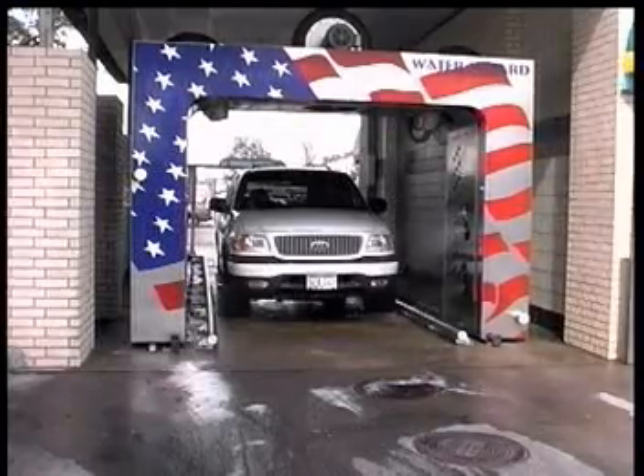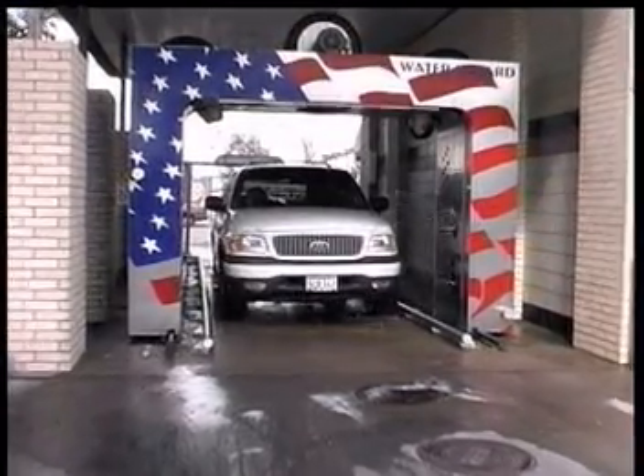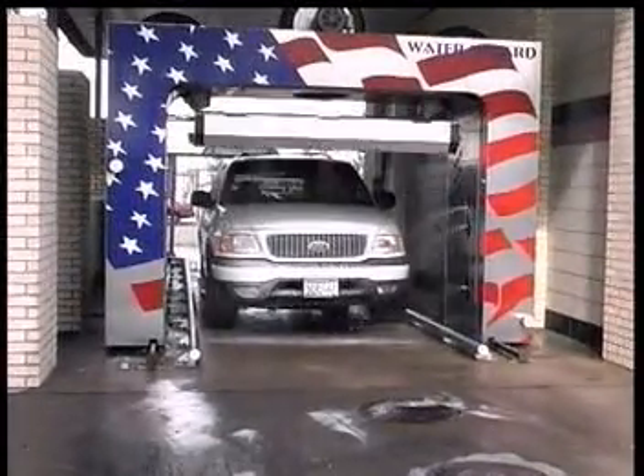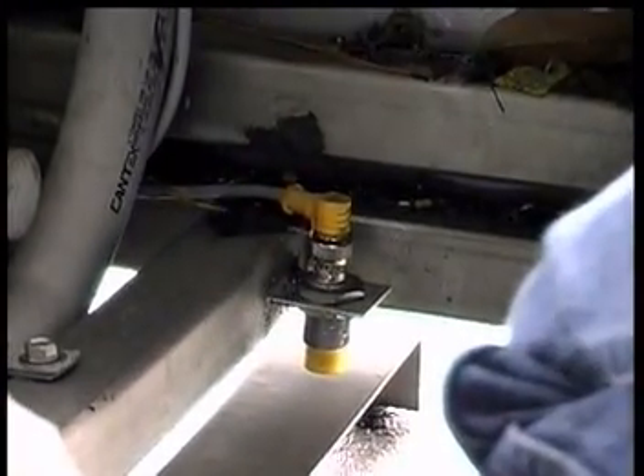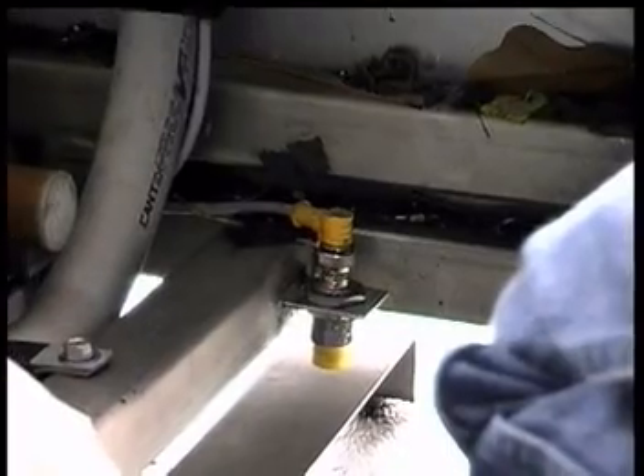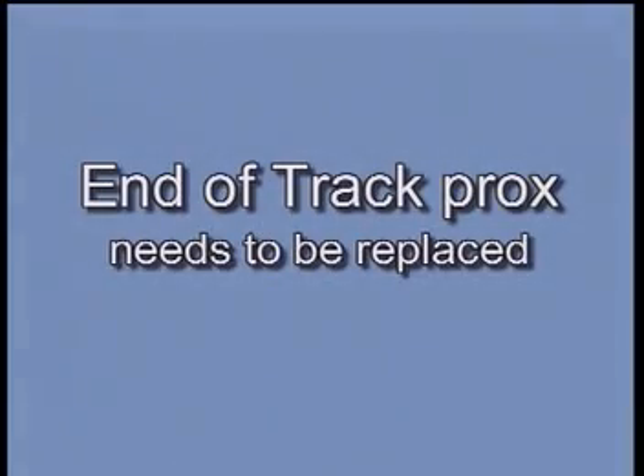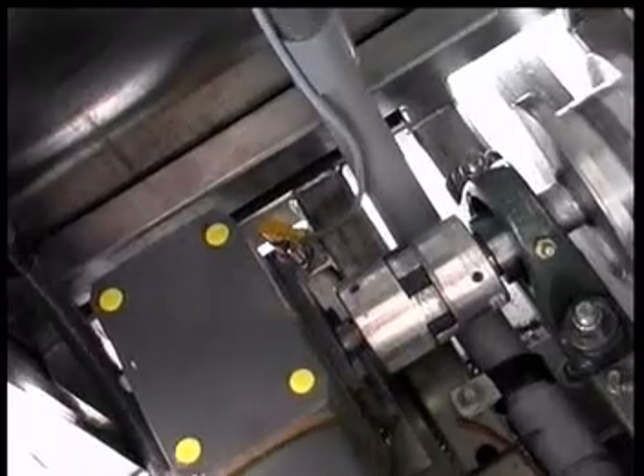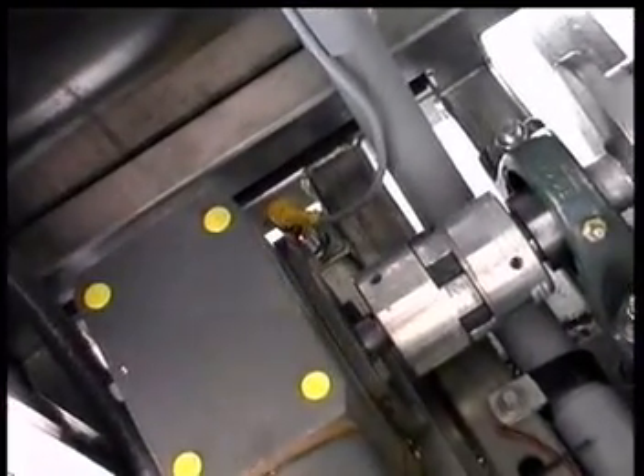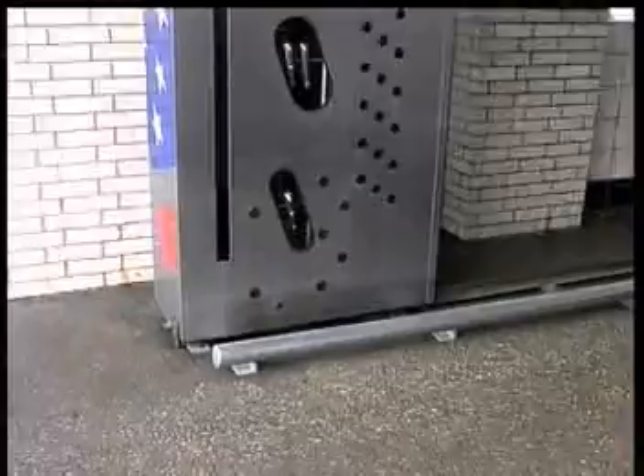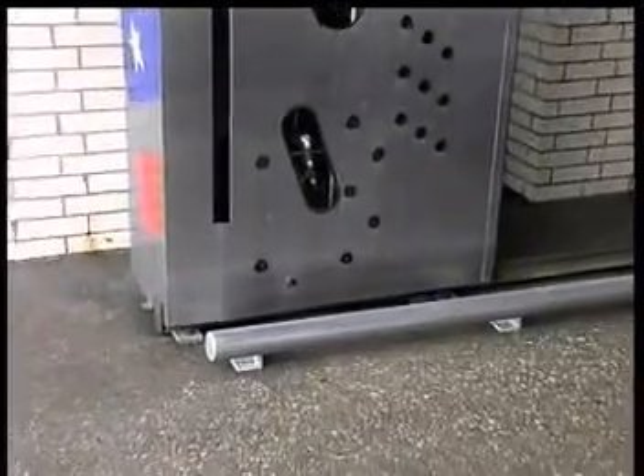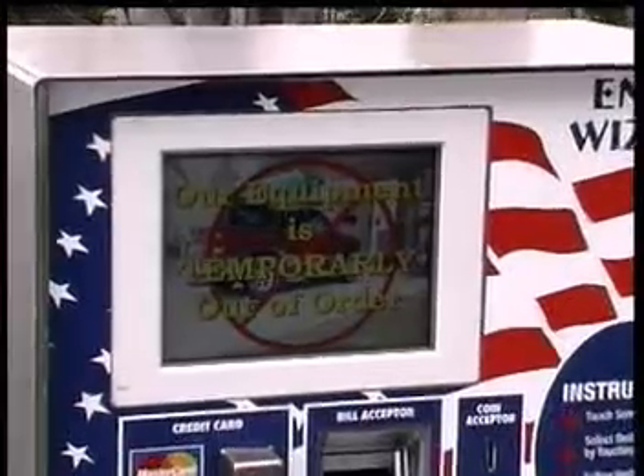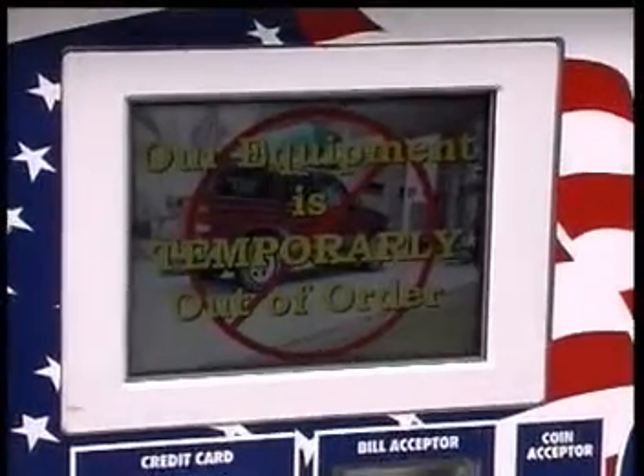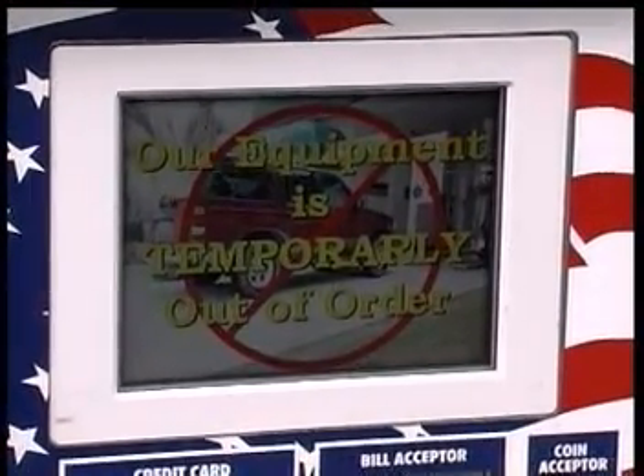This program tests the operation of the home prox during the first 1 second of the wash cycle. The proximity switch should be on at this time. This prox is tested during the first 1 second of the wash, and the program looks to see if it is off. If the prox is on with the gantry in the home position, then we display this message and disable the entrance controller. See Chapter 8 for troubleshooting the prox switch.